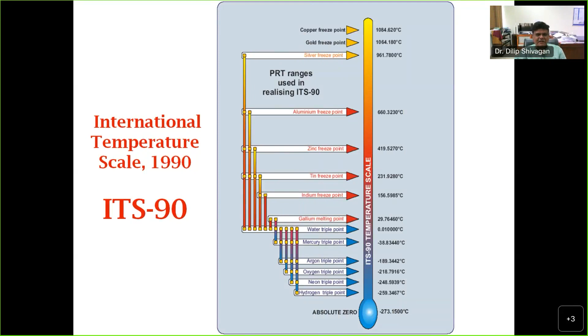Okay, so these are the fixed points defined in ITS 90. You can see the metal in a graphite crucible, and such an SPRT is used, immersed in this fixed point, so that we can make the measurement. For radiation thermometers, there are black bodies and standard pyrometers, or earlier we had the tungsten strip lamp as a standard, and then black body. These were earlier traceable to PTB. Now we have established this facility up to 3000 with our own traceability.